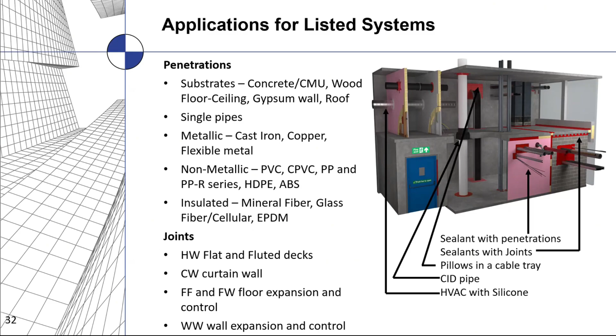So all of that is replaced, as you're seeing here, with firestop sealants, pillows, putties, and all different types of materials used to seal these openings for different kinds of construction — concrete, block, wood, gypsum, any kind of material. It can be anything from a single pipe, plastic or metal, to multiple penetrations all ganged together through one single opening, as you saw in some of those fire tests. And there can be joints all around the structure — at the edge of walls, across rooms, from ceiling to floor, roof to basement — opened any way you can imagine.